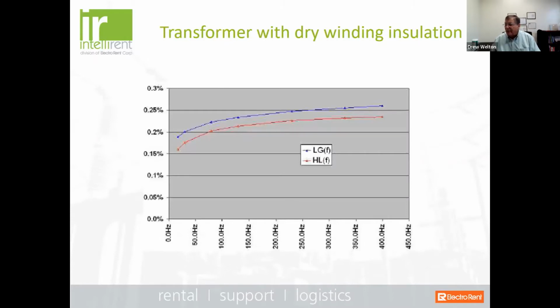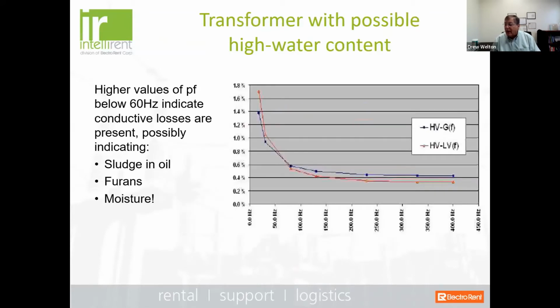And this is actually a case study that we did on a number of different transformers. So right here, if you see your power factor measurements at values lower than the 60 hertz or 50 hertz nominal, that's a transformer with dry winding insulation. You can feel pretty confident. Now, on the other hand, if you have higher values of power factor below 60 hertz, that is an indication you've got possible conductive losses. And conductive losses can be sludge or furans or inert furans, but it also could be moisture. So that should be a red flag right away.